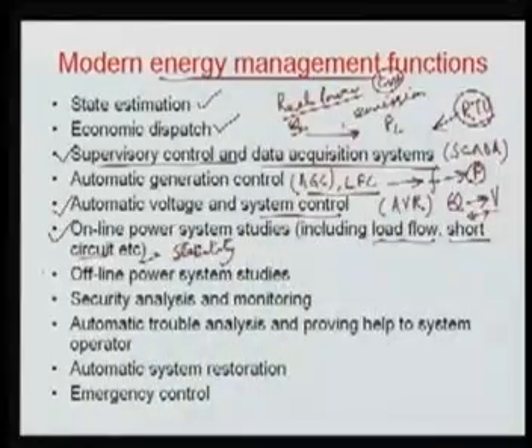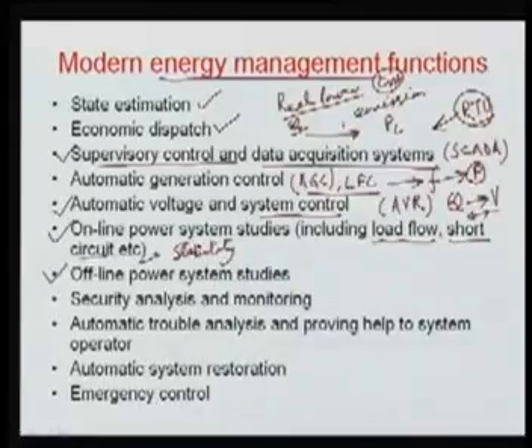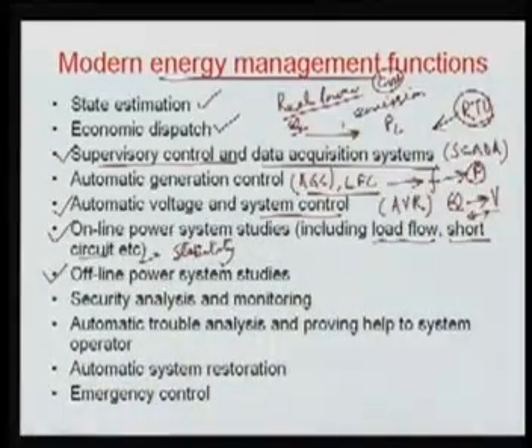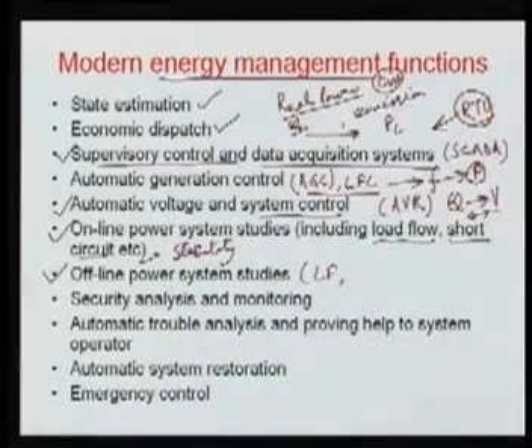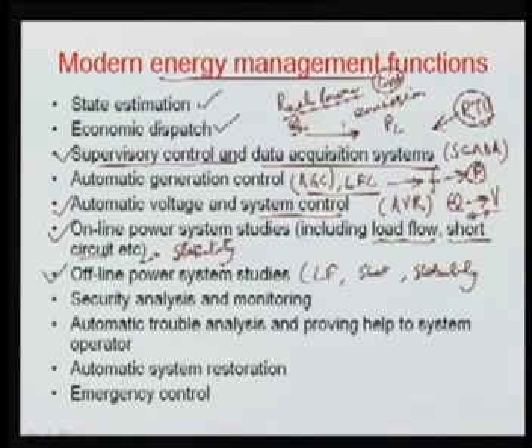Another energy management function is your offline power system studies. These are also studies similar to your online ones, but they are done offline. It means there is no need to go online every time, because it is a very time consuming process. Here we calculate short circuit, stability and load flow. So some of the studies we can perform offline so that we can see the system performance for our analysis and other monitoring purposes. So these also include your load flow, your short circuit and your stability studies.